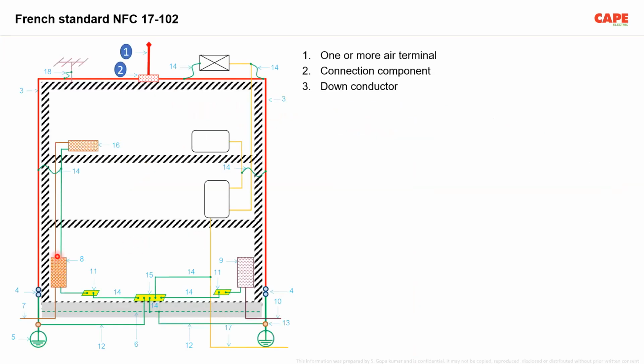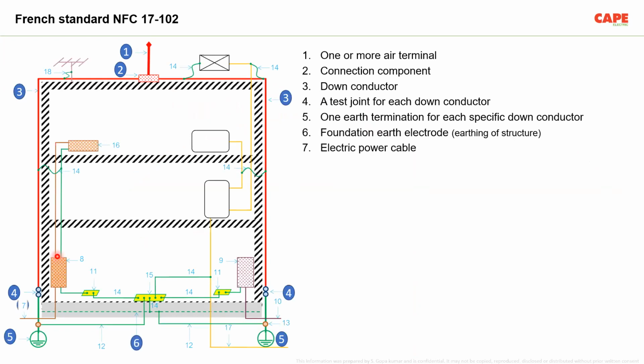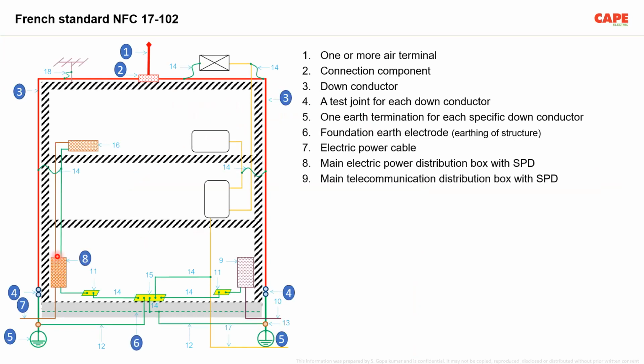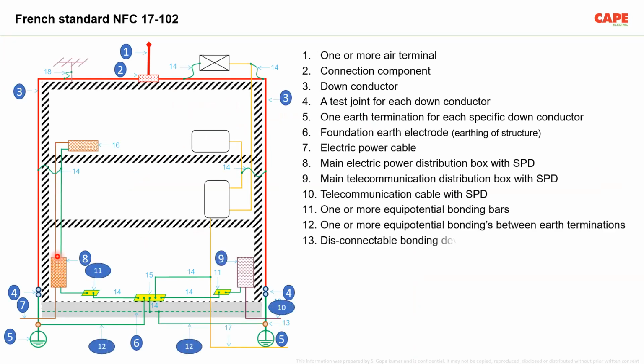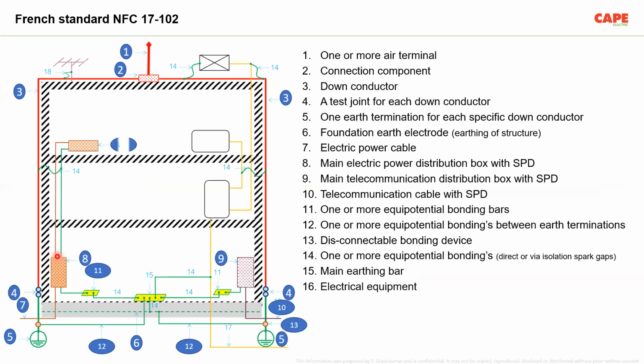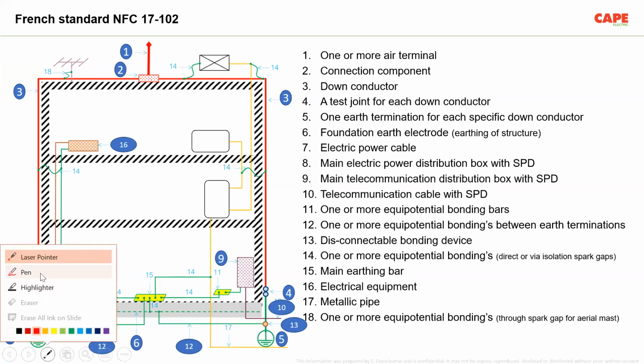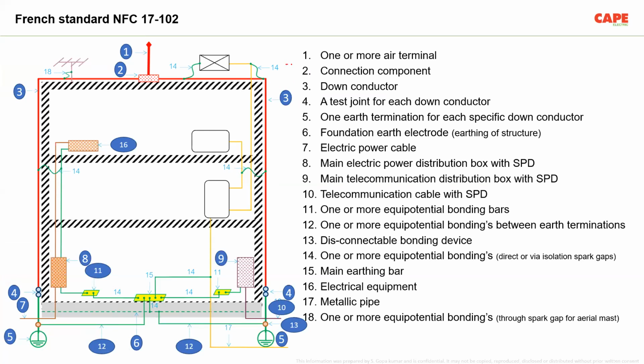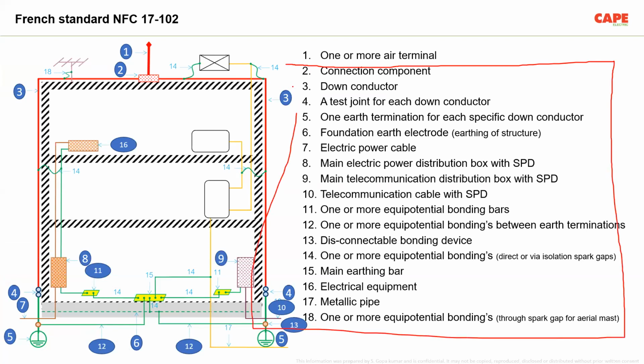So this French code is available. The English version is available for free download on some websites. You just type NFC 17102 and you can download it. Actually, this picture I took from the French code itself. It says there are 1 to 18 items required to protect a building, serial number 1 to serial number 18. I don't want to go deep. Now, if you look at the Indian standard or IEC 62305, the IEC says for your lightning protection, you need to have item numbers 2 to 18.